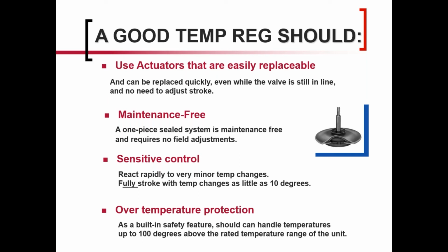Maintenance free, same thing. The actuator, the thermal fill, is the most critical part of these valves. If you lose fill or you don't have the right amount of fill, any brand, ours, anybody's, then they're not going to operate accurately or correctly. If you lose thermal fill, a lot of times they won't close or open when they're supposed to, period. So maintenance free, where you've got a one-piece system, for lack of a better word, is the ideal approach, where you minimize leakage and leak points.